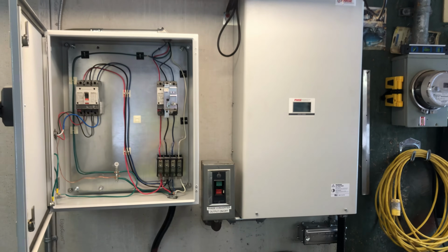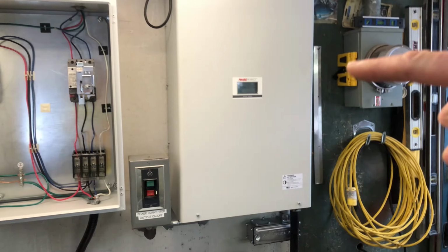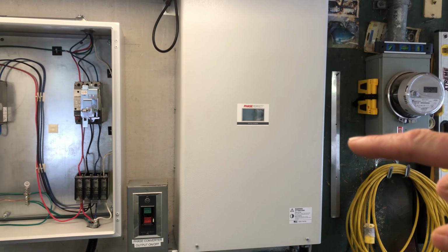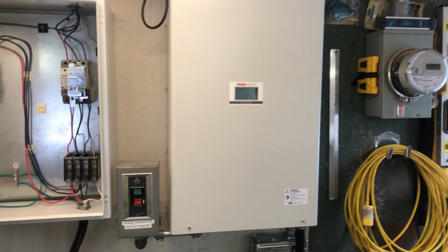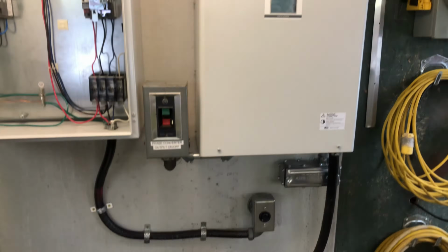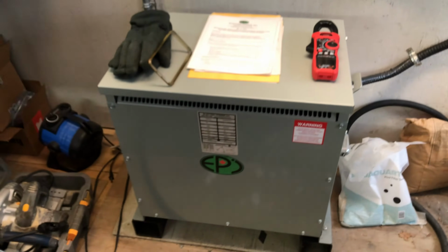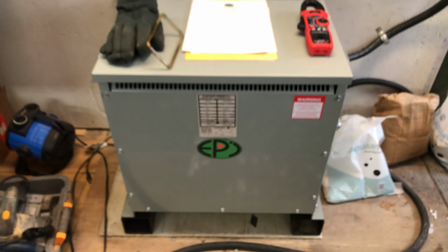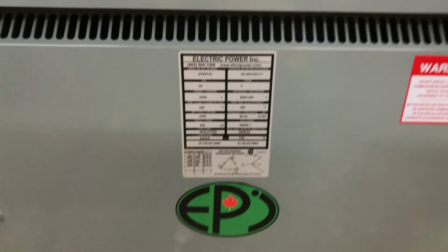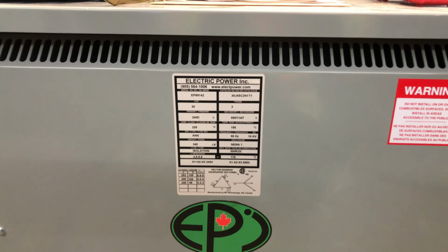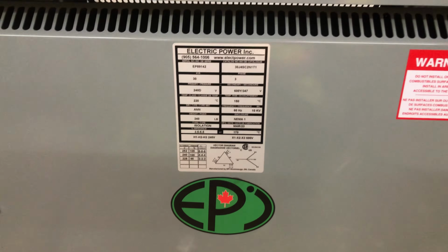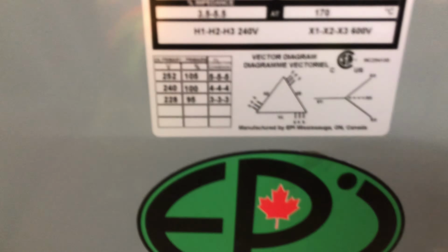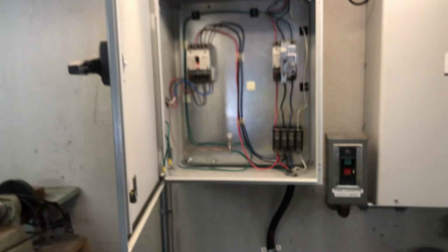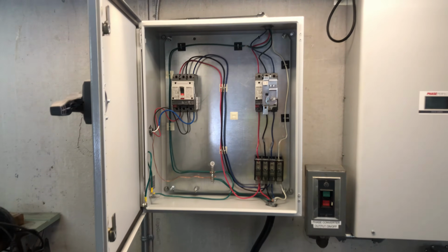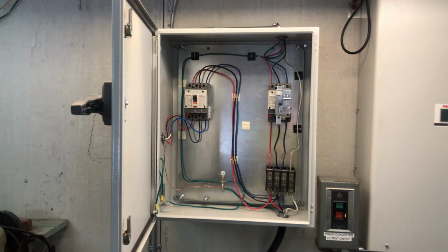Okay, so with all the doors open here, we'll quickly go over it. Single phase to 3-phase digital phase converter from Phase Technologies, Phase Perfect, 20 horsepower. Power comes out of it 3-phase with a high leg, goes to this 600 volt 3-phase converter from 240 volts to 600 volts, and this is an isolating transformer, so it's a delta Y, and that gets rid of the high leg, so you don't have to worry about high voltages from ground to any leg, or to the one high leg.